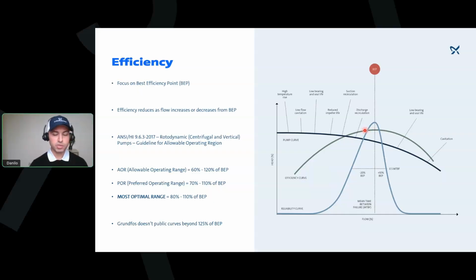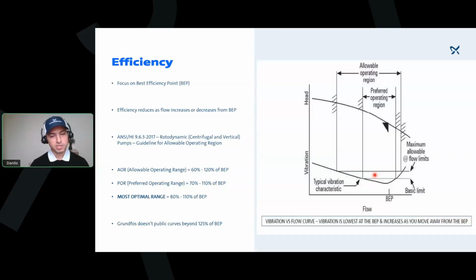Another thing I want to mention is, I want to bring another slide here so you can see. Okay, a similar curve here, if we only look at the pump curve. So here I have a little picture of what you can see on the preferred operating range, compared also to the allowable operating range, right?